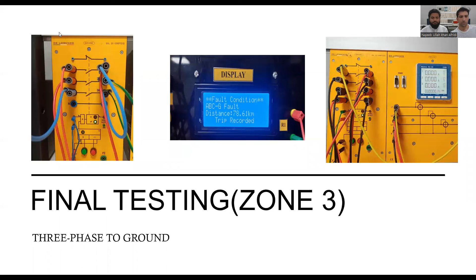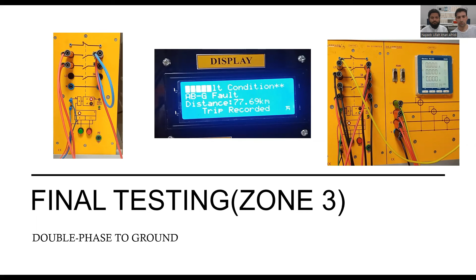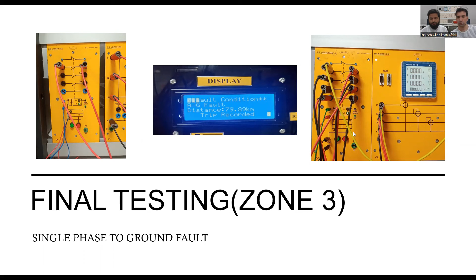Similarly, we give a three-phase to ground fault in zone 3, and our relay takes a 750 millisecond delay and then generates a trip signal and isolates the fault. This is the fault breaker, from where we give the fault to the system. Now we give a double phase to ground fault in zone 3, and the values are shown in the display. Then we give a single phase to ground fault, and we can see that the fault occurred in the third zone at approximately 80 kilometers, a phase A to ground fault. We can see that the fault is successfully isolated, the breaker is in off status, and we have no current in the power system.